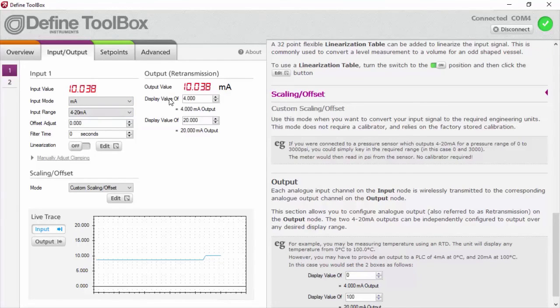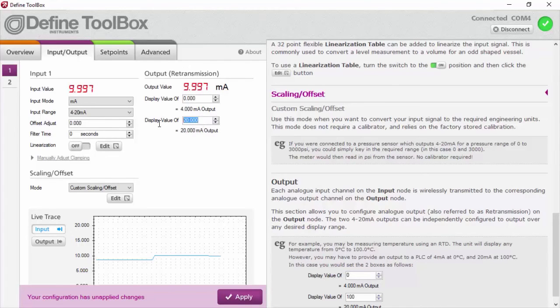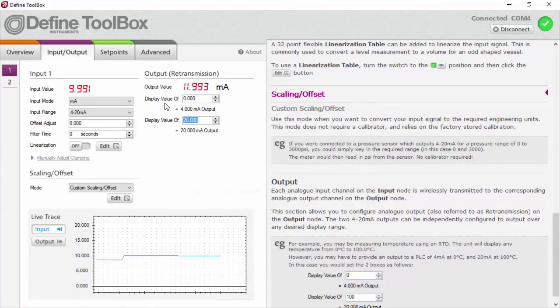The retransmission is still showing for a display value of 4, an output value of 4 milliamps. That's actually a bit confusing at the moment because that 4 is now 4 feet, and that's not really going to mean anything to us. So it'd be much better to say that a display value of 0, which is 0 feet of water, is going to be 4 milliamps. And let's say that the top of my tank is 20 feet, so now that's going to be 20 milliamps. So it's nice to note that we don't actually have to put 34.6 feet in here again, so we're using a different scaling for the input and for the output. So if I click apply, you can see that the output value has now changed, and that is scaled now for the extents of our tank being on that 4 to 20 milliamp output.